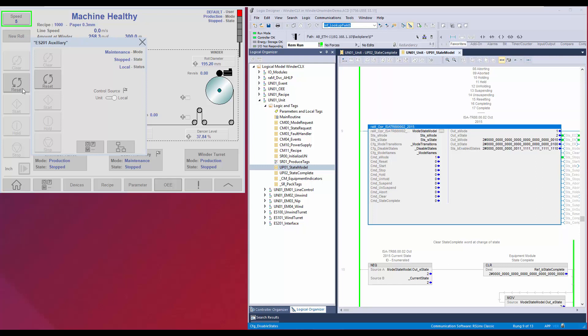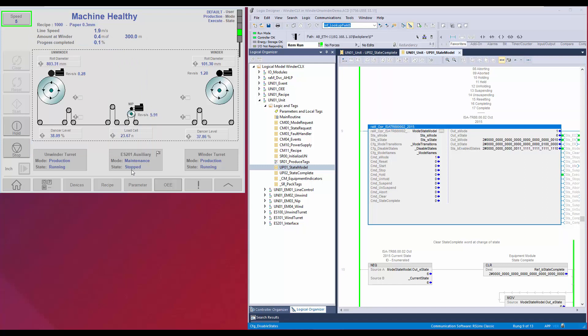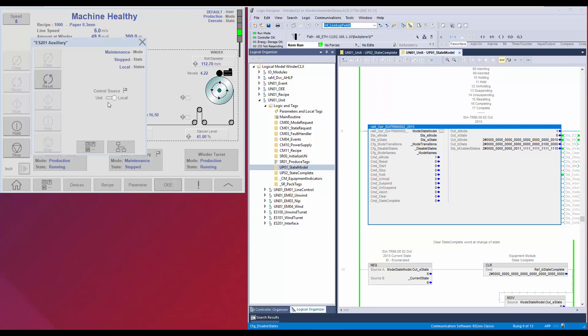While the auxiliary equipment supervisor is in maintenance, I will go ahead and reset and run the machine. Now the machine is in production and in execute state while the auxiliary is in maintenance and in stop state. Once the maintenance is done, I will switch the auxiliary to unit control. You can see the mode is changed automatically to production and the equipment supervisor is commanded to go to running state. The status is shown as remote and linked. Now the auxiliary is in sync with the unit state model.